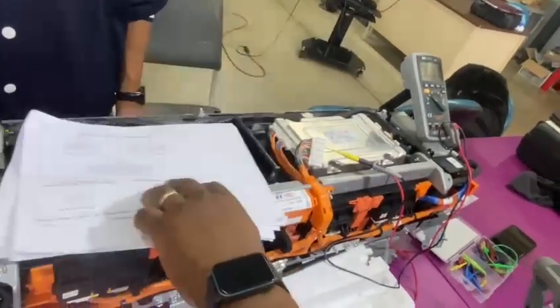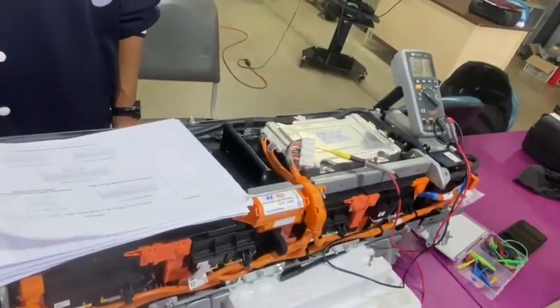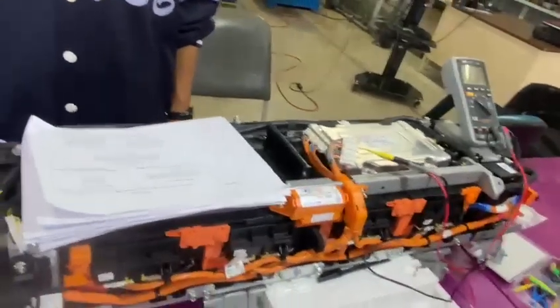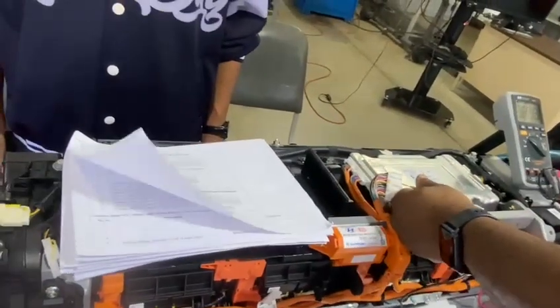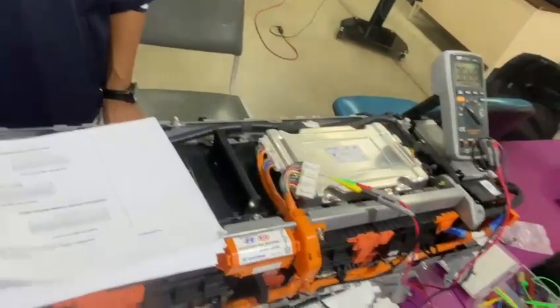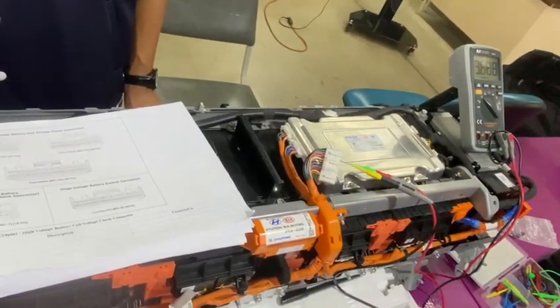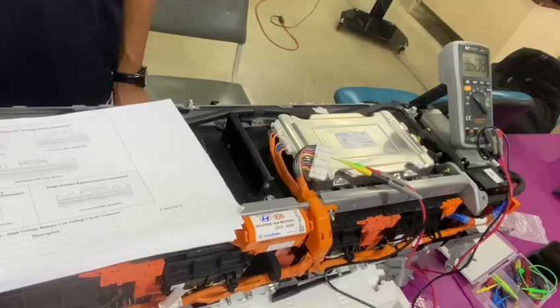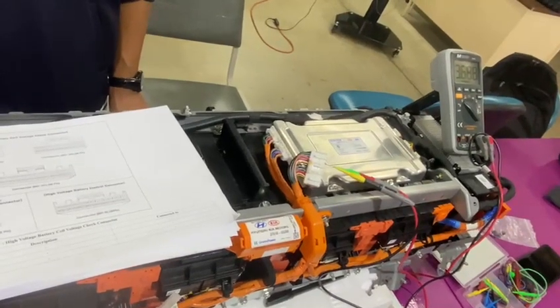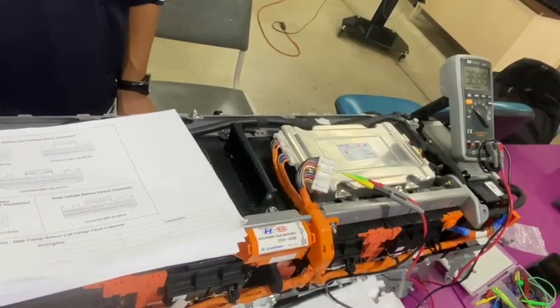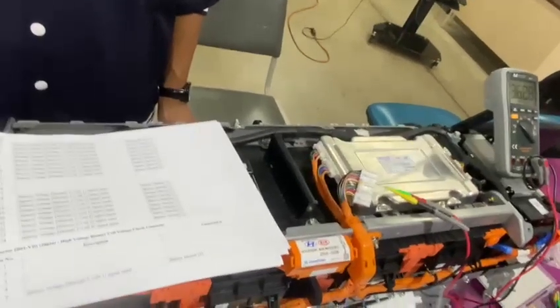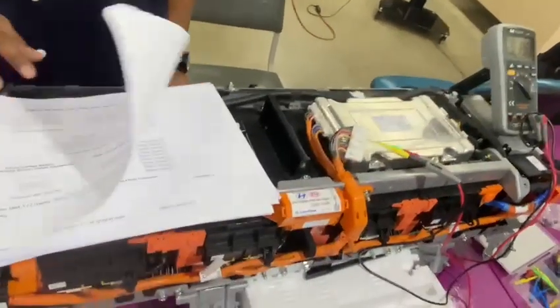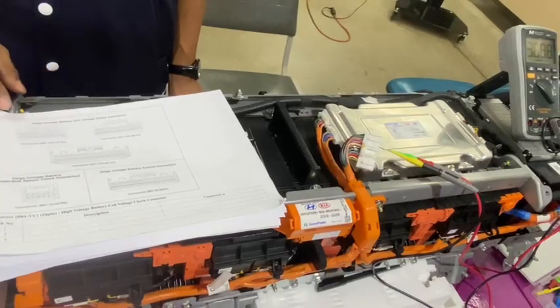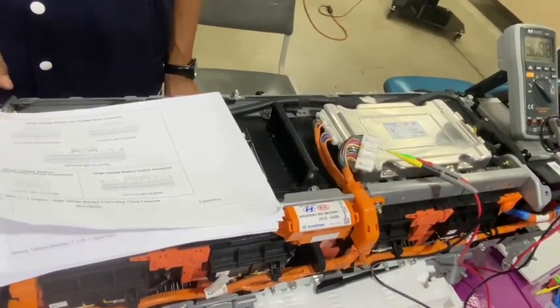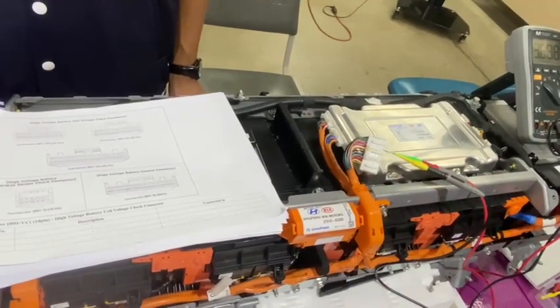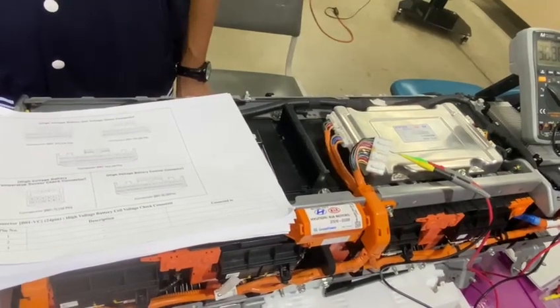My best explanation for this variation could also be a defective BMS - not a straight short or defect, but rather the BMS sometimes communicating and then not communicating. It could be imbalanced, not properly balancing the cells, causing this imbalance. It's my belief a replacement BMS may bring the modules back into line with each other, or worst case scenario, we may have to replace the entire battery pack.